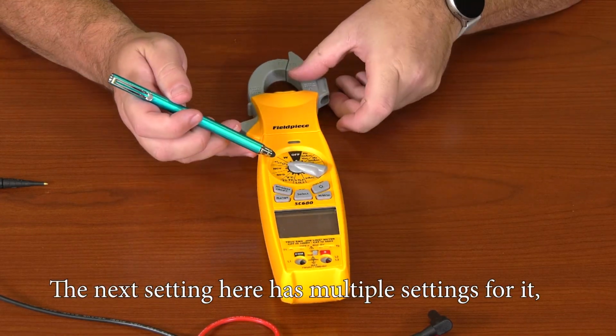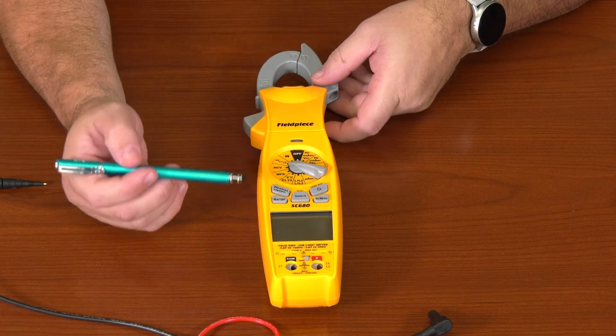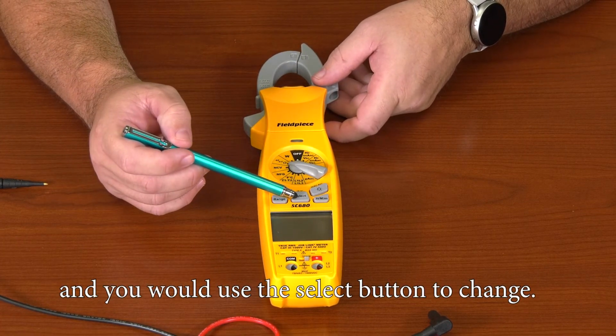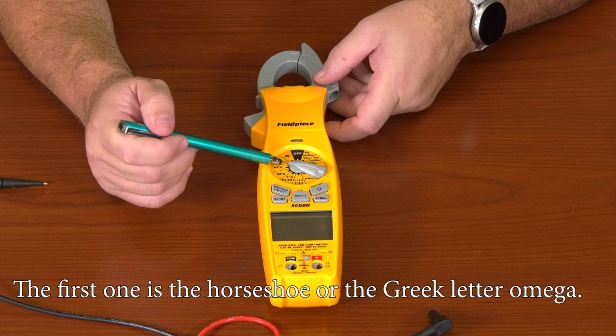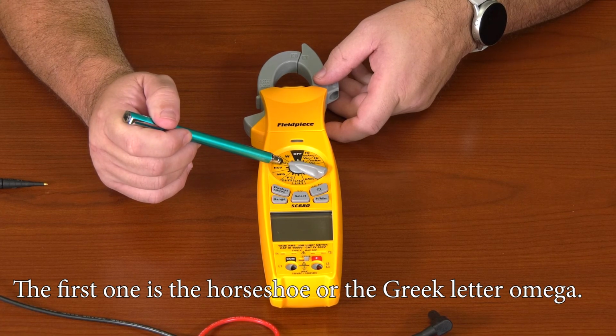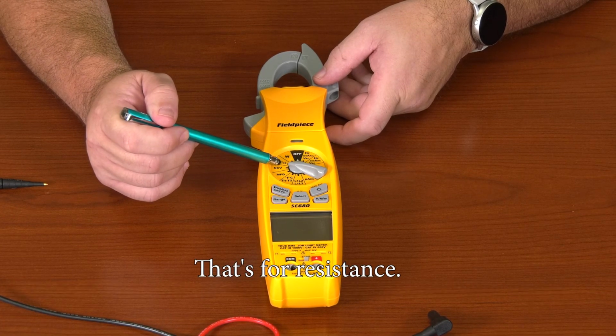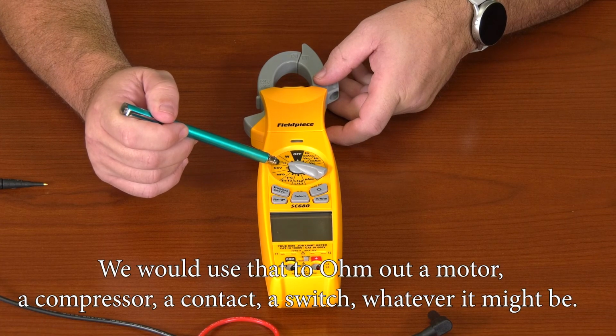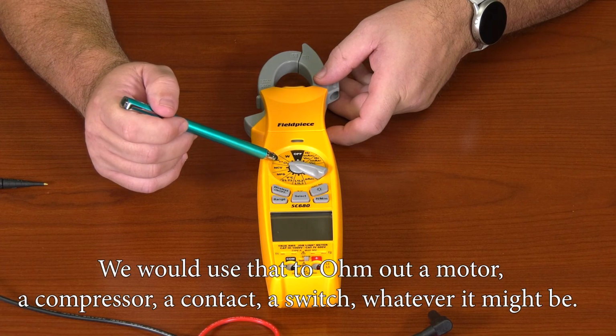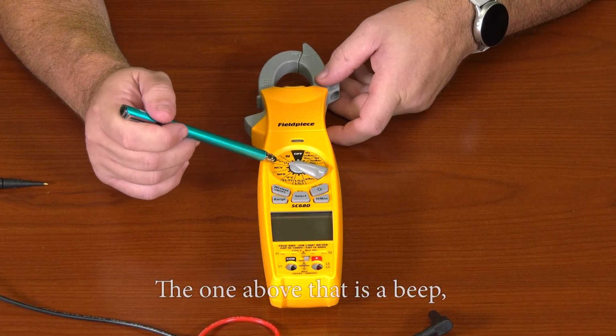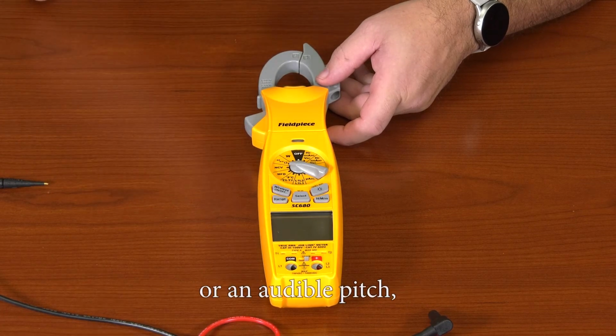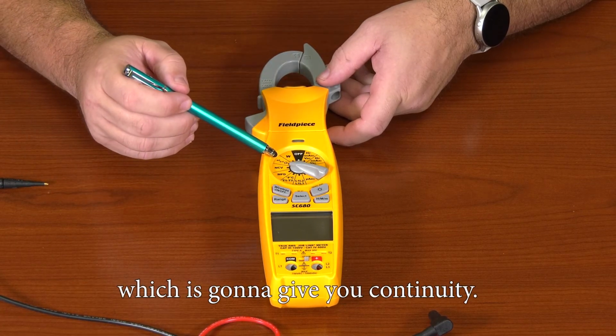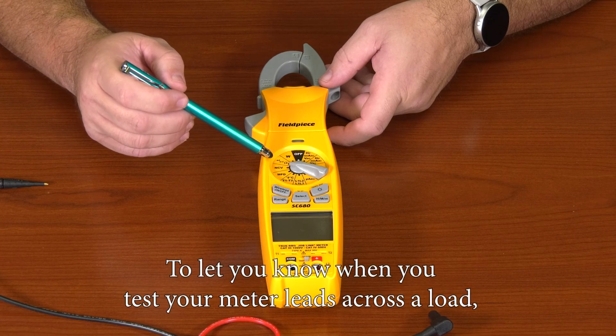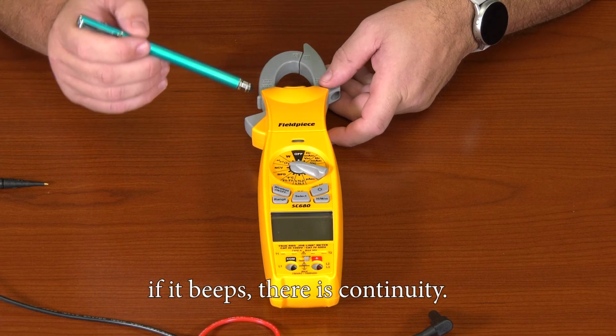The next setting here has multiple settings for it, and you would use the select button to change. The first one is the horseshoe or the Greek letter omega. That's for resistance. We would use that to ohm out a motor, a compressor, a contact, a switch, whatever it might be. The one above that is a beep or an audible pitch, which is going to give you continuity to let you know when you test your meter leads across the load, if it beeps, there is continuity.